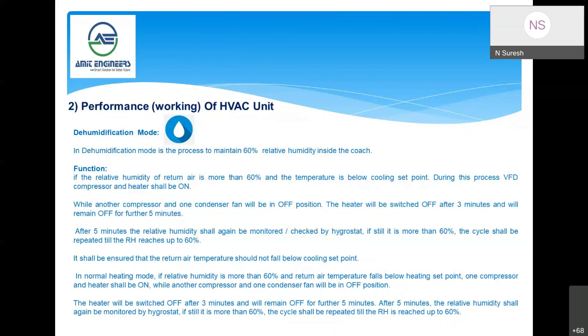So if the relative humidity of the return air is more than 60% and the temperature is below the cooling set point, during this process the VFD compressor and heater shall be on, while the other compressor and one condenser fan will be in off position. The heater will switch off after 3 minutes and will remain off for a further 5 minutes. After 5 minutes, the relative humidity shall again be checked by the hygrostat, and if it is more than 60%, the same cycle will repeat until the RH is below 60%. It shall be ensured that the return air temperature does not fall below the cooling set point. In normal heating mode, if the relative humidity is more than 60% and the return air temperature falls below the heating set point, one compressor and heater shall be on. So this is basically the logic of the dehumidification mode.